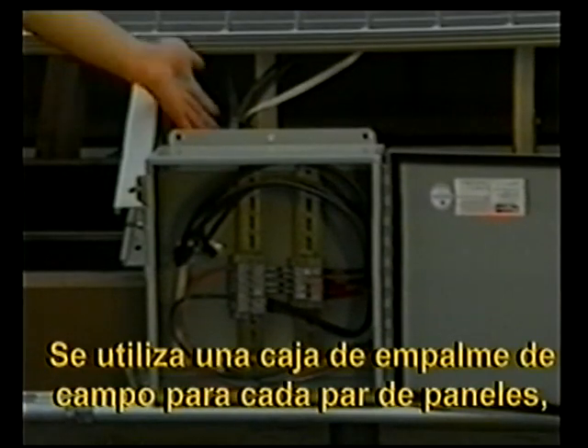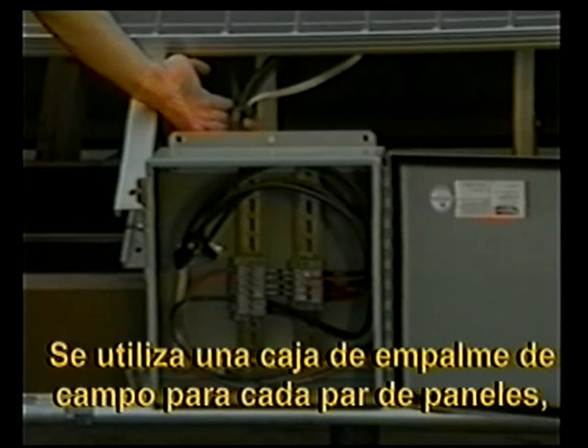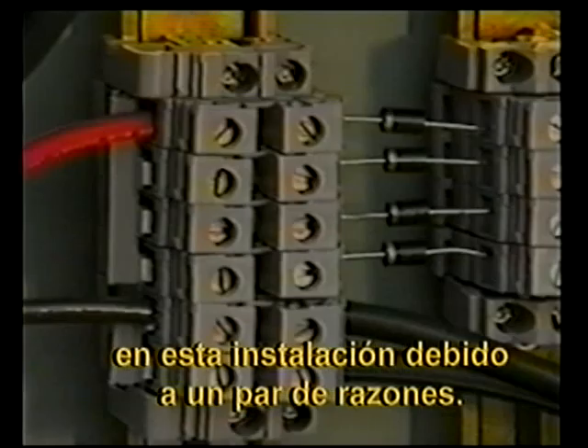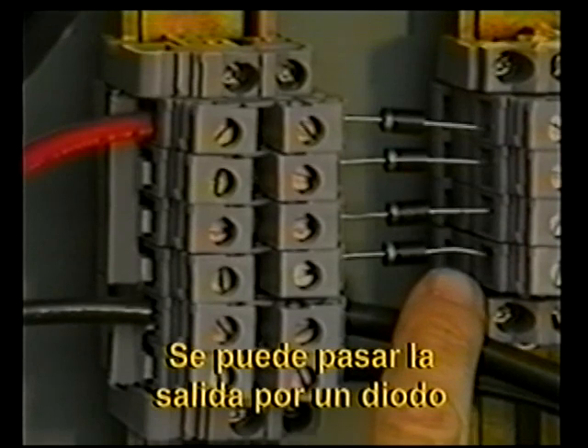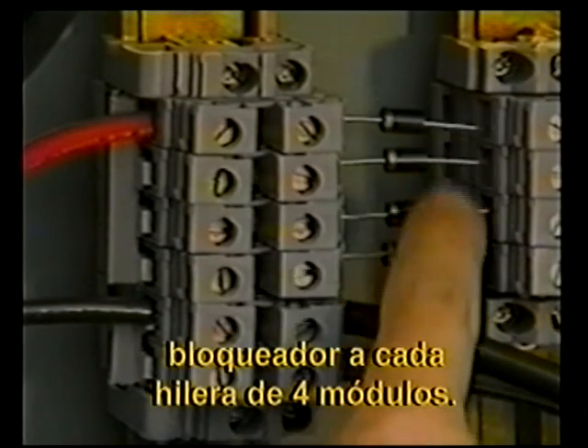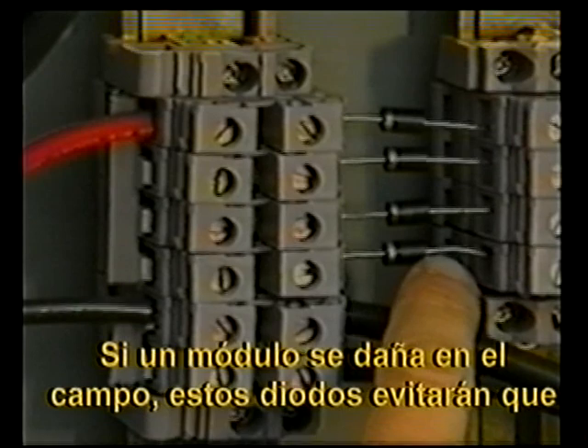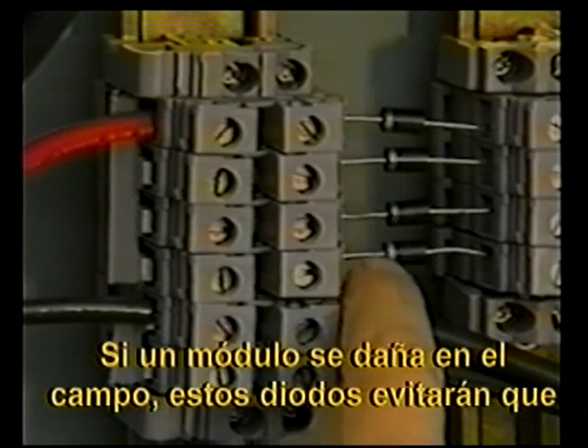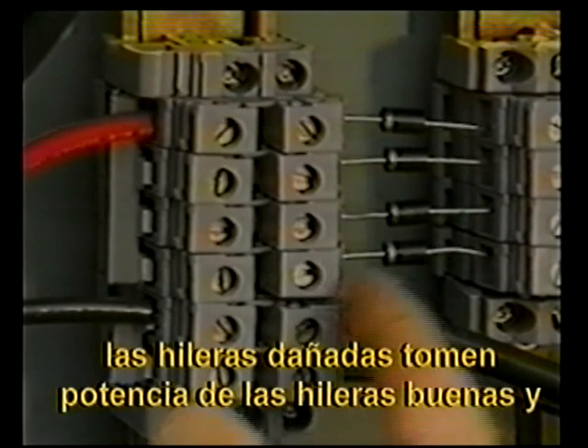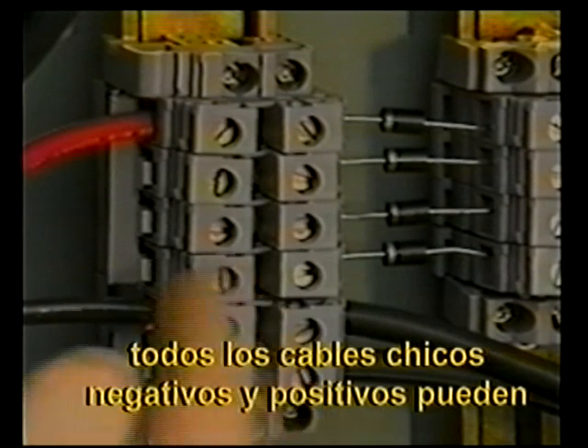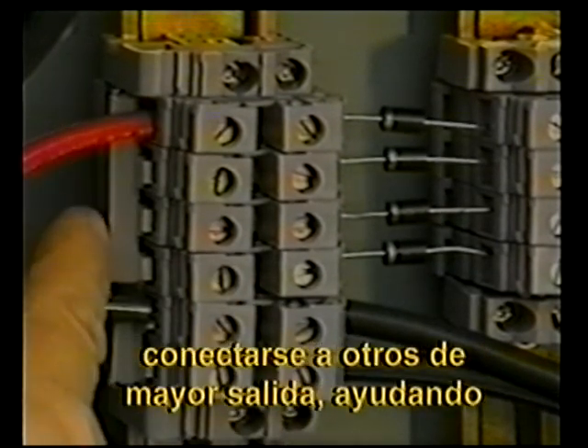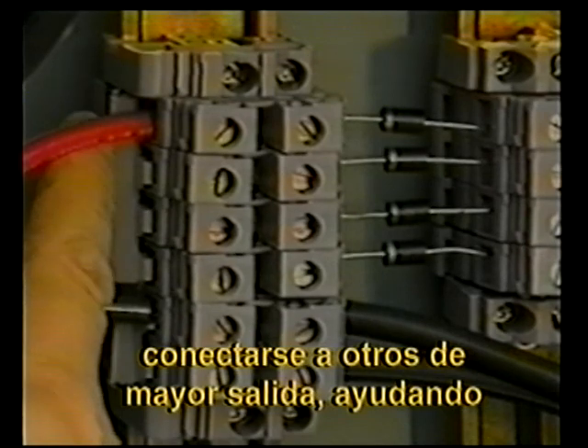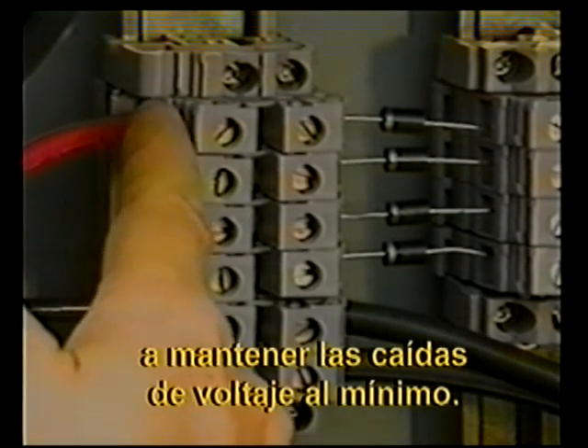A field junction box is used for each pair of panels in this installation for a couple of reasons. Each 4-module string can have its output pass through a blocking diode. If a module becomes damaged in the field, these diodes will prevent the damaged string from drawing power from the good strings. And all the small positive and negative wires can be connected to larger output wires to help keep voltage drops to a minimum.